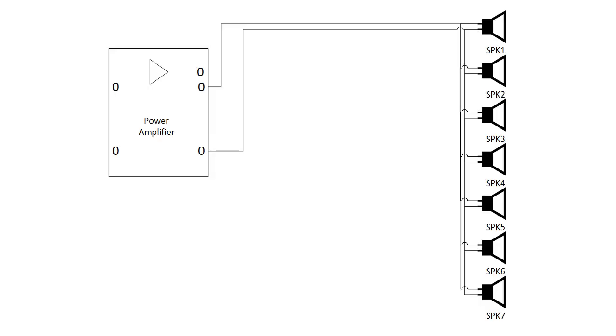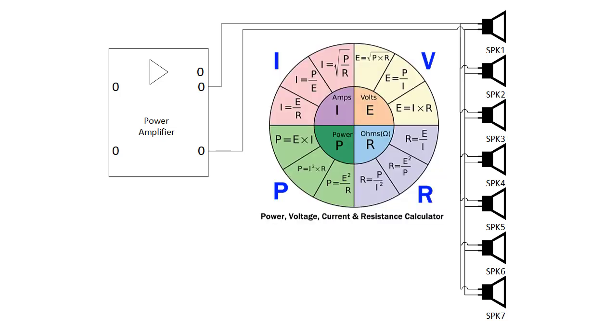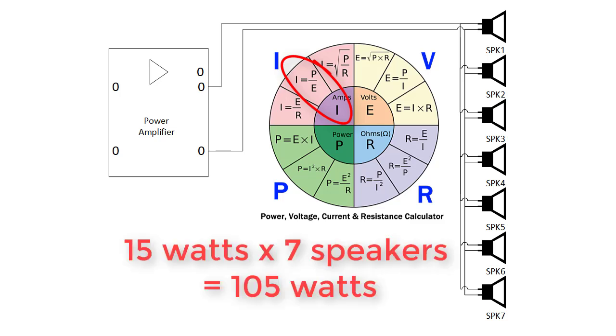Let's say we're putting together a 70 volt distributed sound system with 7 speakers that are each tapped at 15 watts, and it has a 120 watt amplifier. We need to know what cable to use, so using our handy chart here, we have a voltage of 70.7 volts, and know that the total power of all 7 speakers is 15 watts times 7, or about 105 watts.